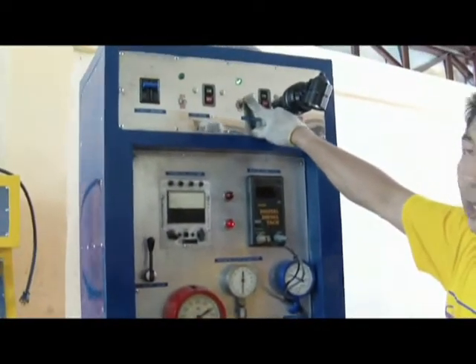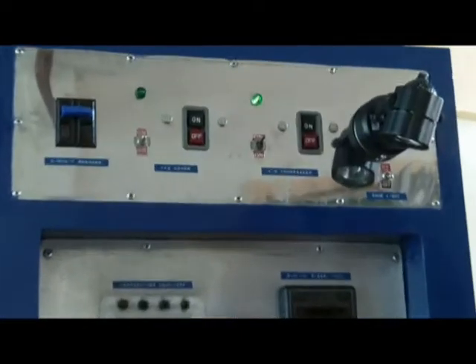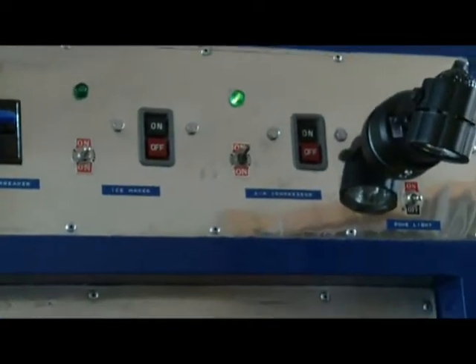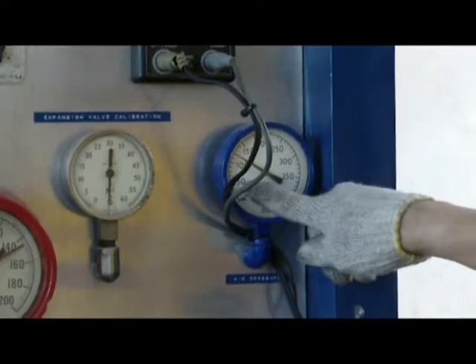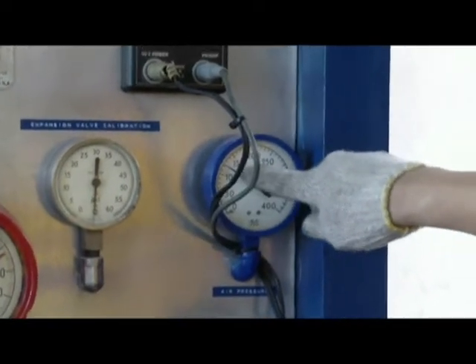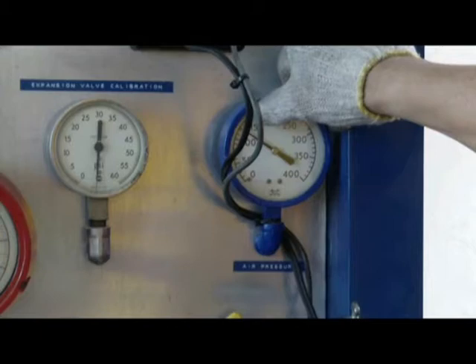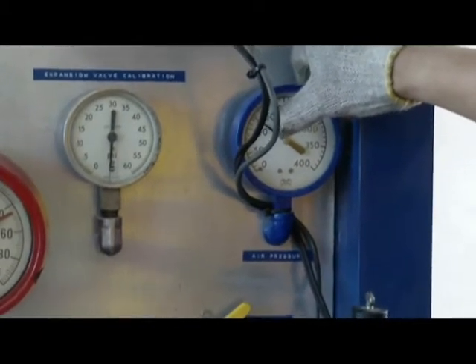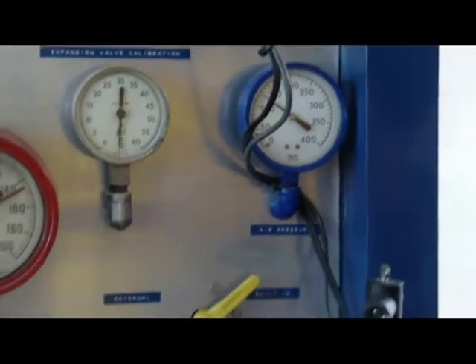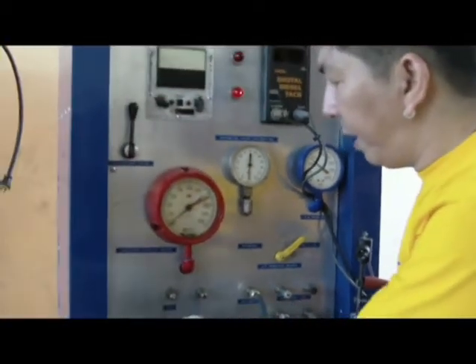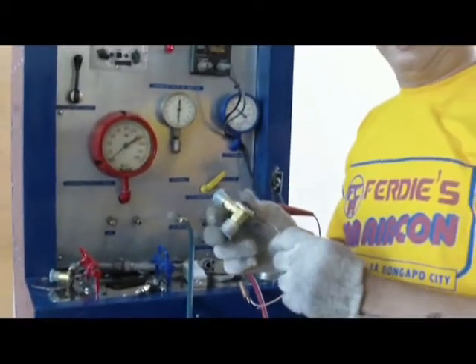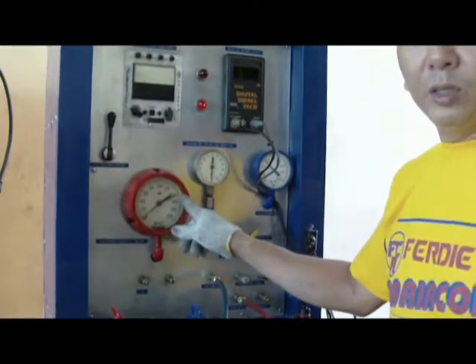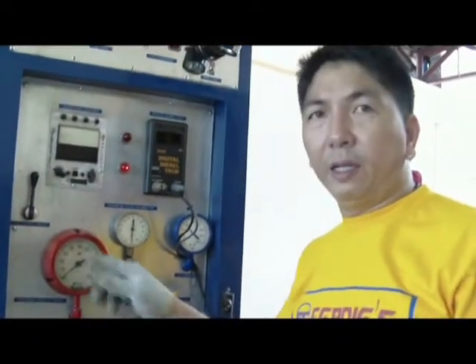And there's an automatic switch that will turn on the air compressor when it reaches 100 psi, and when it reaches 150 psi it will shut off the compressor automatically. So what I'm gonna do is look for an expansion valve that I will calibrate, or I will put in this pickup here, that will match compressor capacity of around 150 to 140 psi.